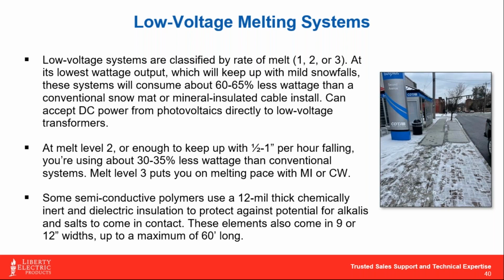Things like steps, we can certainly snow melt. MI cable is a much better product for doing step systems versus mats. The mats tend to buckle a little under the weight of the concrete - not that it impairs them physically, but we don't want the weight to shift the cable position so it touches against itself inside the pour, or winds up on the riser section of a step instead of on the step itself. That's why we usually suggest something like MI cable for steps.